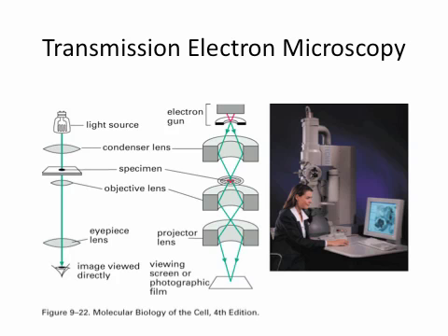If your sample is big and crystalline, the electron gun scatters everywhere. You won't see anything. So you have to have really, really small samples, or you slice it. So you can salami slice it. If you have a big sample, you can embed it in a resin and cut a slice of 100 nanometer thick, put that on your grid, and put it in this machine. Alternatively, very recently we've got a FIB SEM, so you can use an ion beam in order to make the same little slice and use it as a TEM sample. So that sample is tiny compared to a conventional SEM sample.